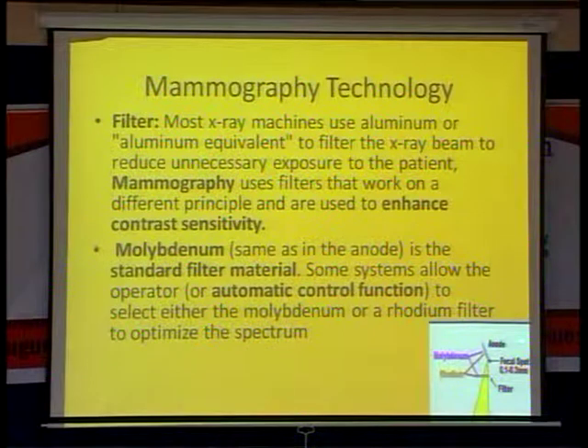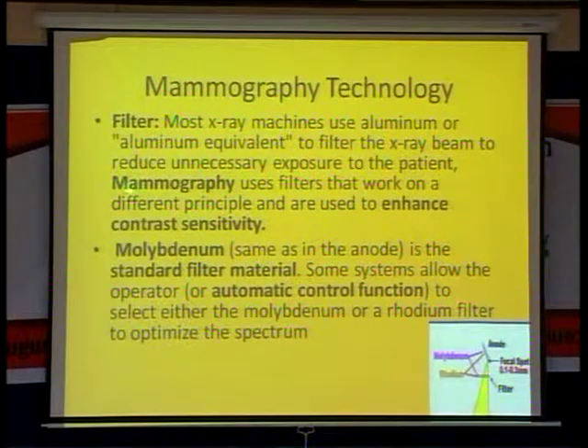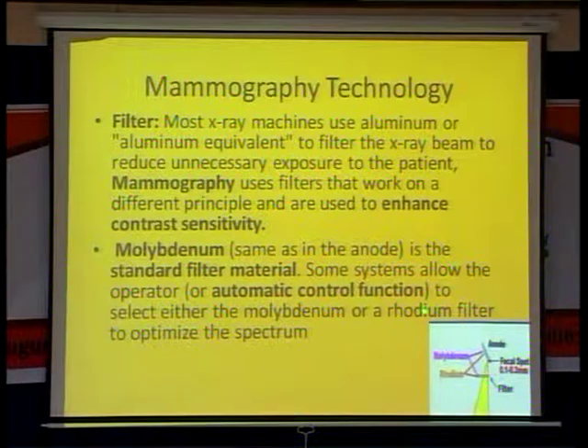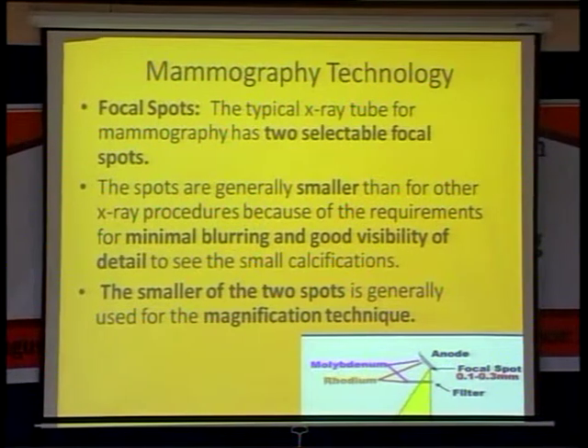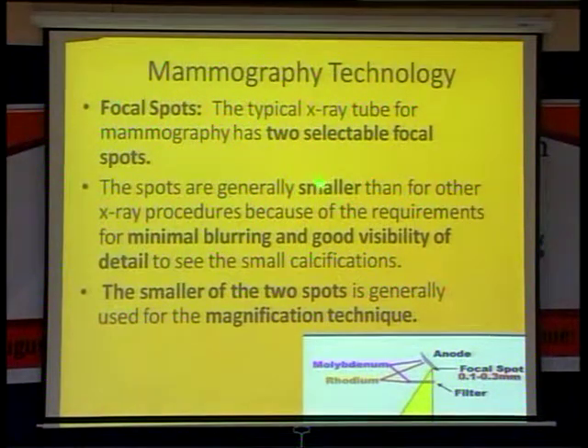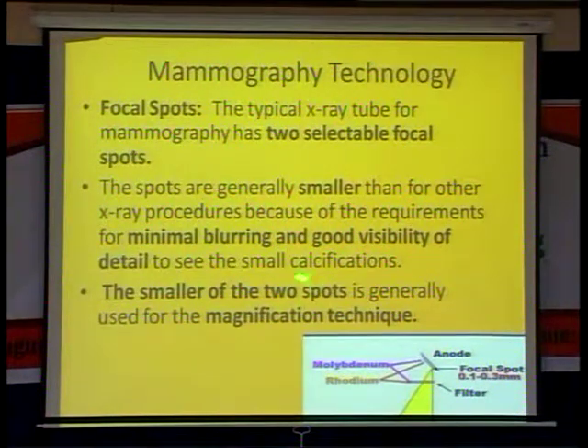Next is the filter. Usually in general radiology we use aluminum or aluminum equivalent filters, whereas in mammography we use a different principle — molybdenum is used as the filter material. Sometimes in automatic control function, we use rhodium also as a filter. The focal spot is 0.1 to 0.3 mm, with two selectable focal spots: a smaller focal spot for minimal blurring and good visibility of detail, used in mammography.